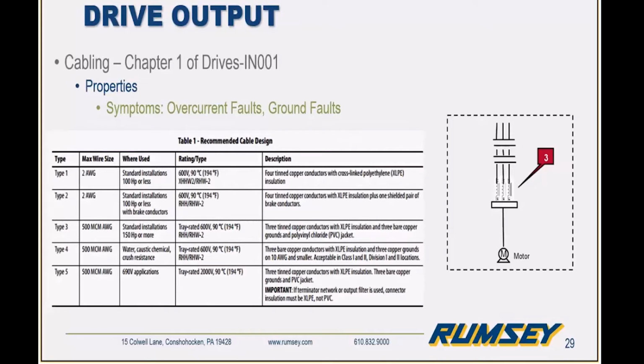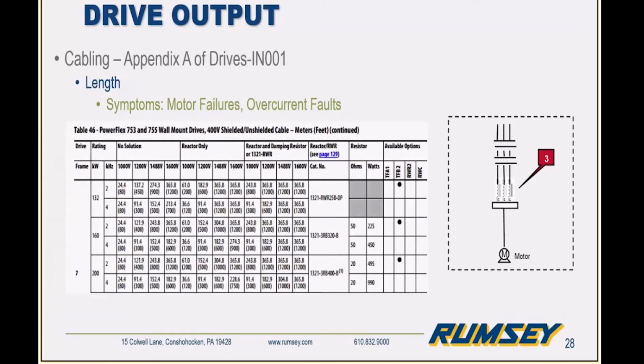So Jared, if I had a motor and looking at that chart, how would I know whether something's 1,000 volt versus 1,600 volt rated? Okay, so really this is going to indicate what the voltage peak is based on the lead length, and if you needed to determine what your insulation rating on your particular motor is, the best way to know for sure would be to consult your motor manufacturer. Another way, if we have, for instance, an MG1 rated motor or inverter duty rated motor, we can know that that's a 1488 voltage rated motor. If it's design B, it may be 1200 or 1000 volt. So again, if you're not aware or sure, it might be best to consult the motor manufacturer.